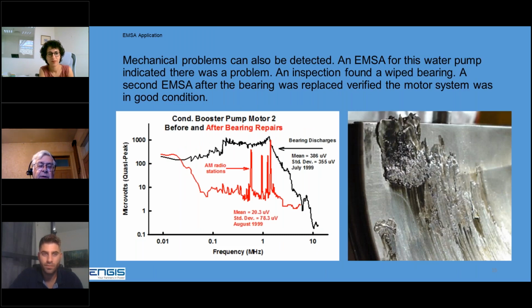One surprise with EMSA was we can pick up stator electrical problems, but we can also identify mechanical problems. Here's an EMSA signature for a water pump that had a problem, and that's the black line. Very high sparking going on. With a sniffer, we determined it was a bearing. They have 3 motors. They only need 2 for operation. So they took it out of service, repaired the motor bearing, put it back in service.